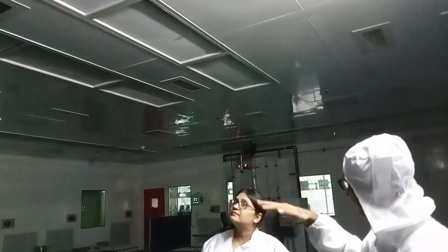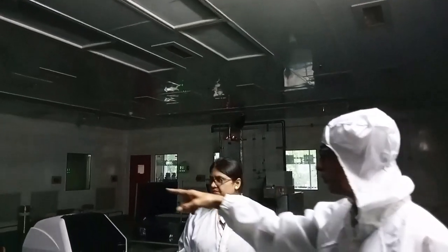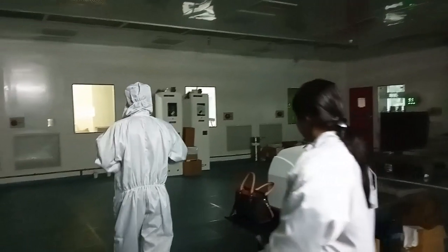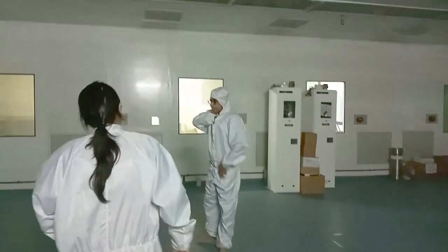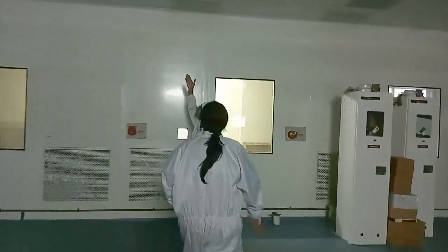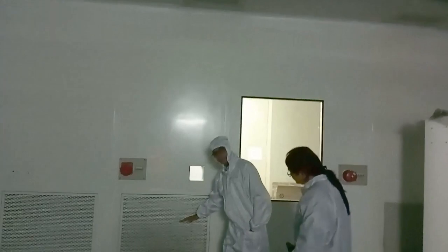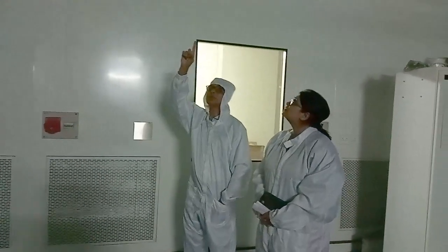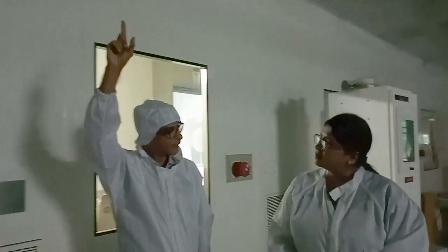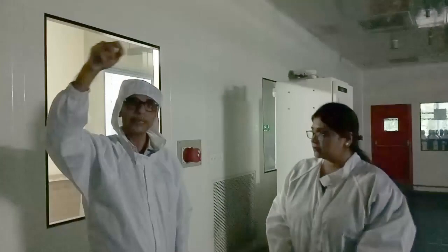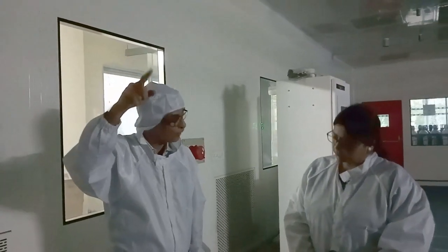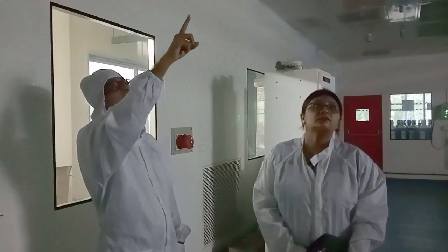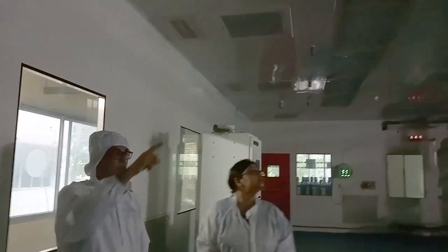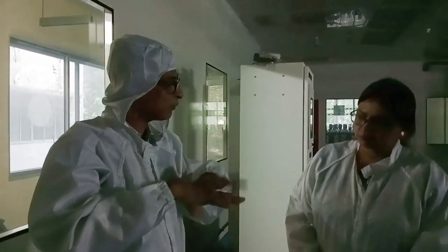that I was discussing before. So air is coming as a streamlined flow. It's very calm and quiet. And those are the chase areas where you can see the air coming and gradually getting out of this filter. Here we have very high quality filters, meaning the air that is generated at that mezzanine floor comes through the ducting layer that we saw on the second floor, and that air is exposed to this clean room through the HEPA filter. The porosity of the HEPA filter is such that it will not allow the dust particles to come in; they will be filtered out.